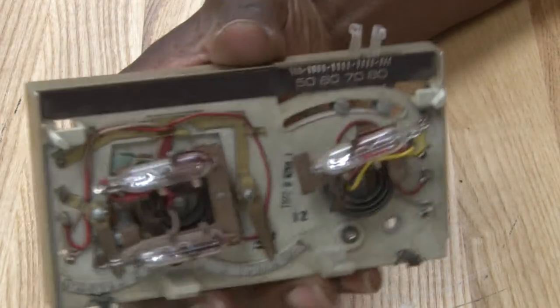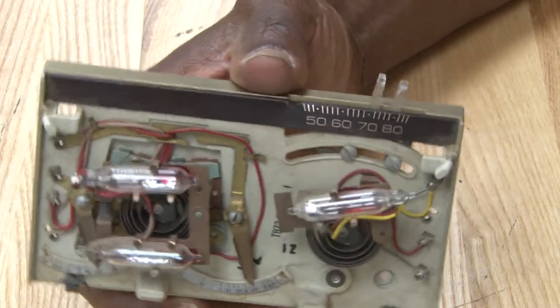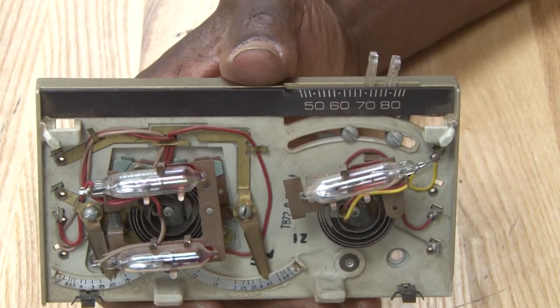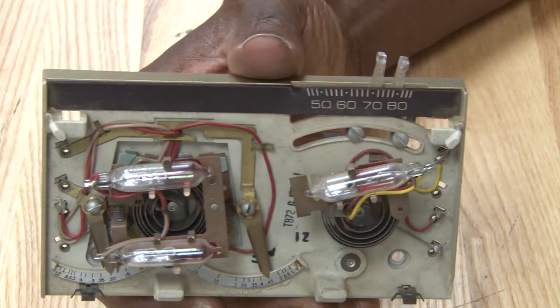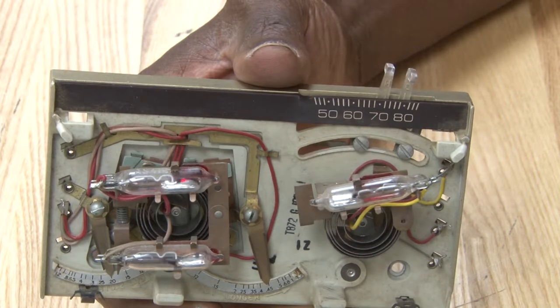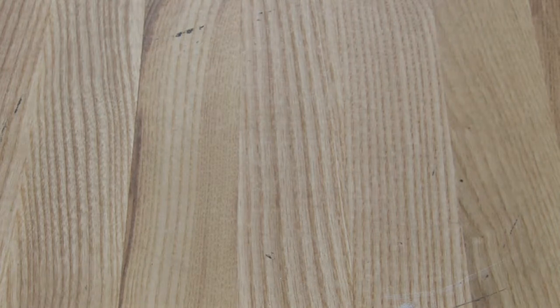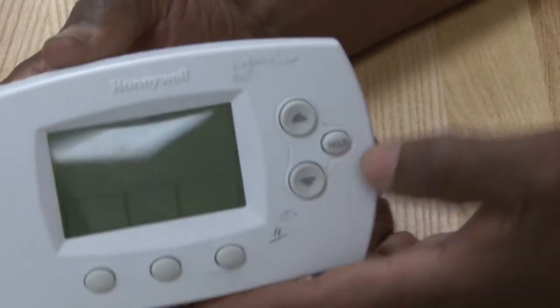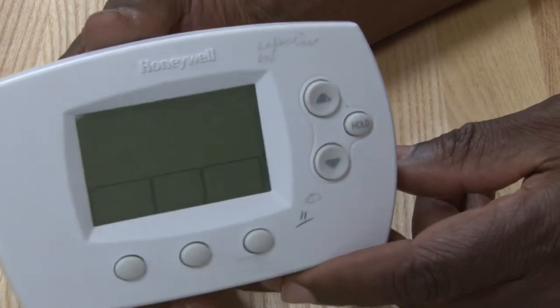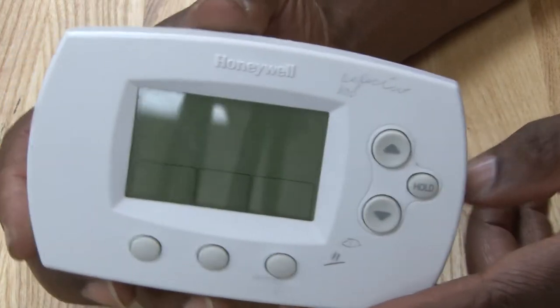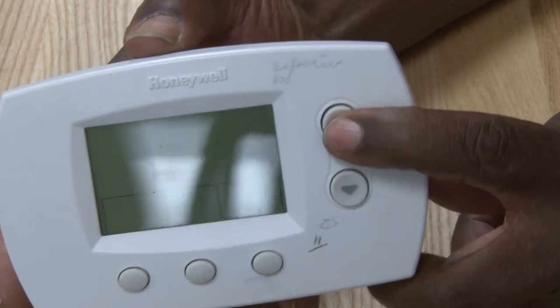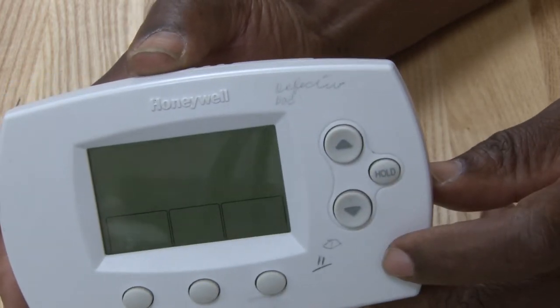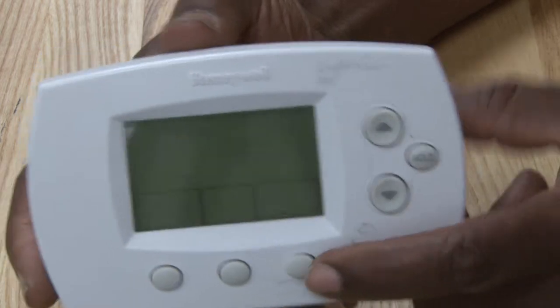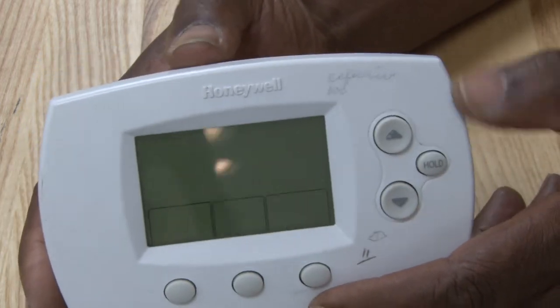This is another type of thermostat, similar, an older style. It's more in commercial buildings where you see a single stage and a two stage, designed for both heating and cooling. Newer type thermostats are, like I said, going to the digital. There are no moving parts. The only moving parts you have are just a push button to raise and lower the temperature or change the programming or to do other things. So it's, like I said, very simple.